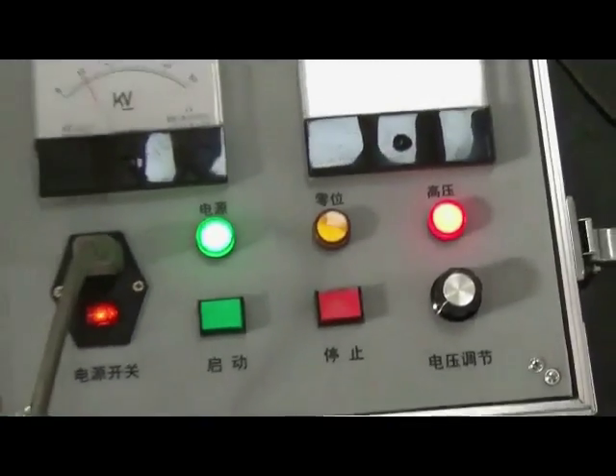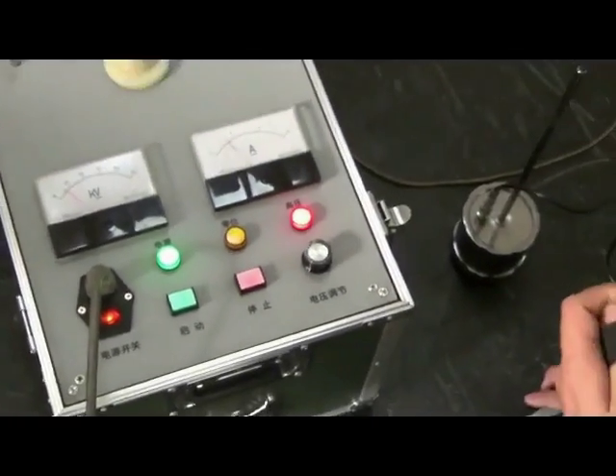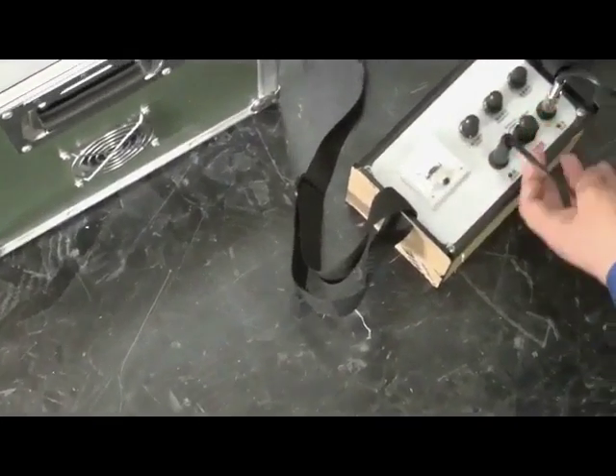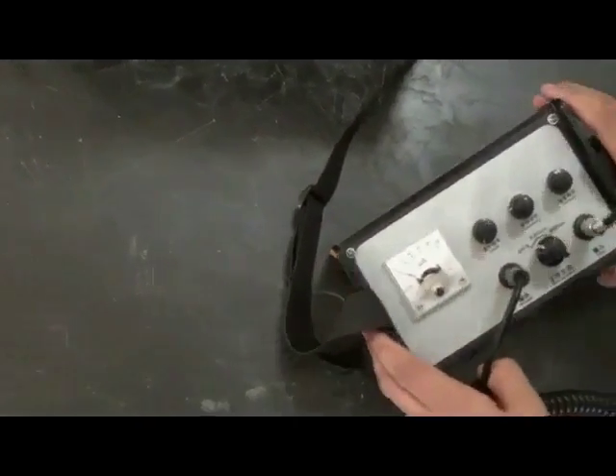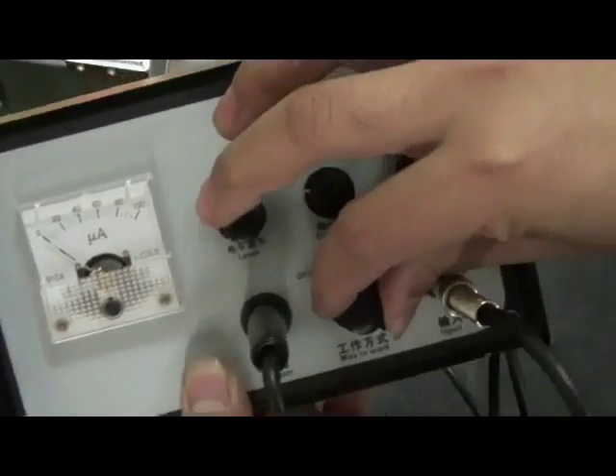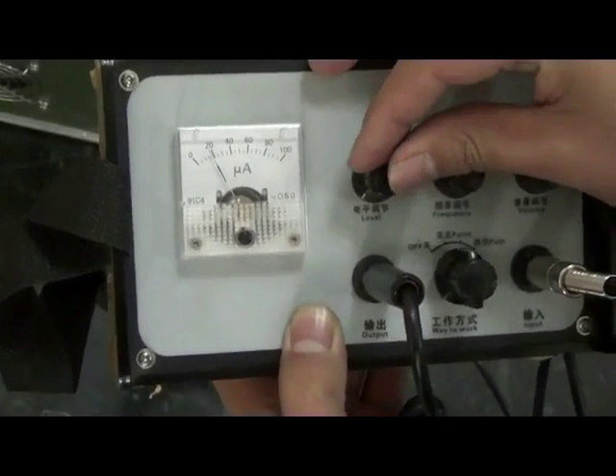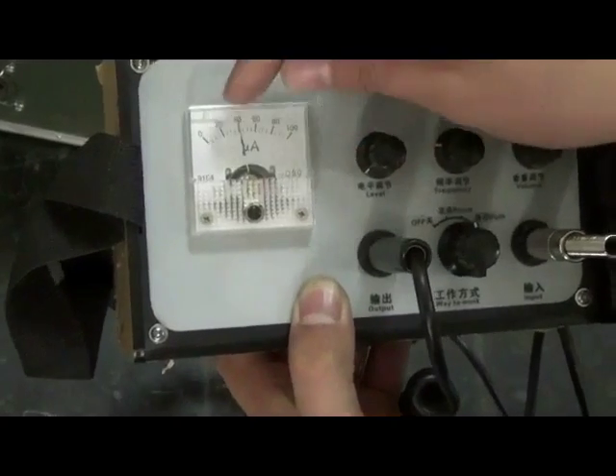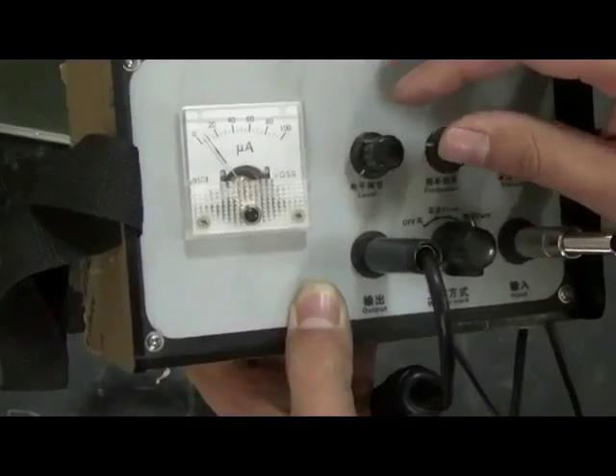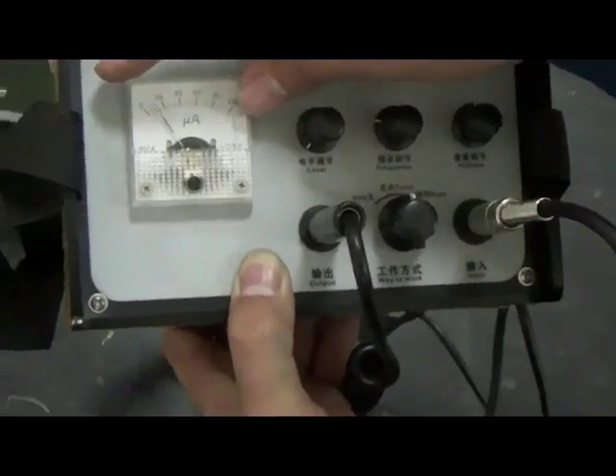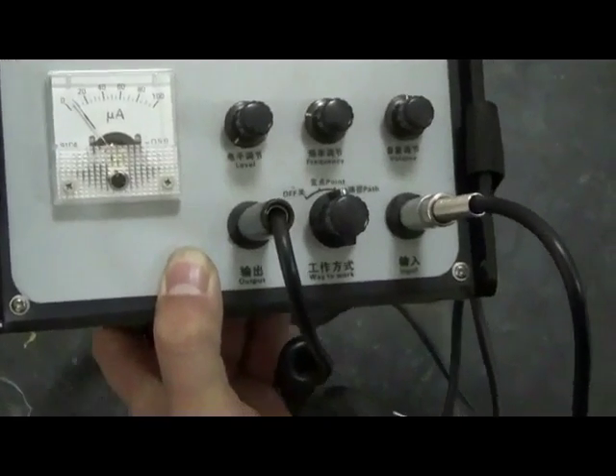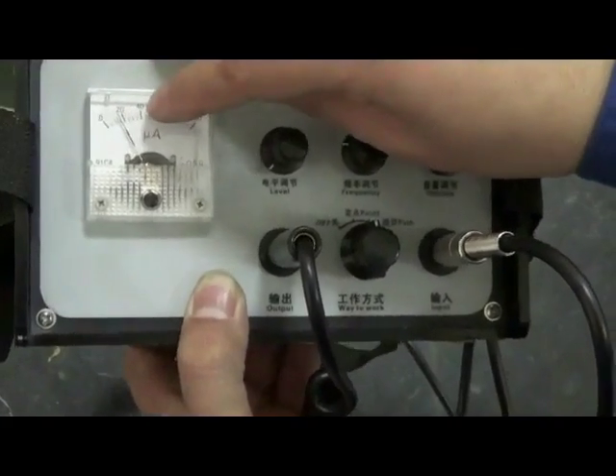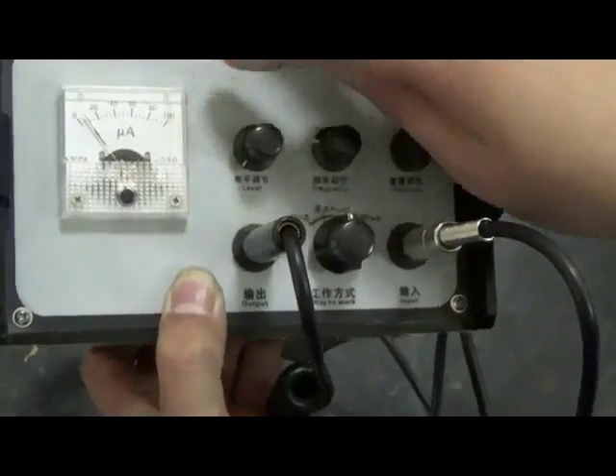Now we use pinpoint locator to detect cable fault. At first, adjust to pinpoint mode. Adjust level. Indicator should be at two-thirds in order to swing well. Notice, when detect rod is right above cable, swing frequency of indicator is same as discharge frequency.